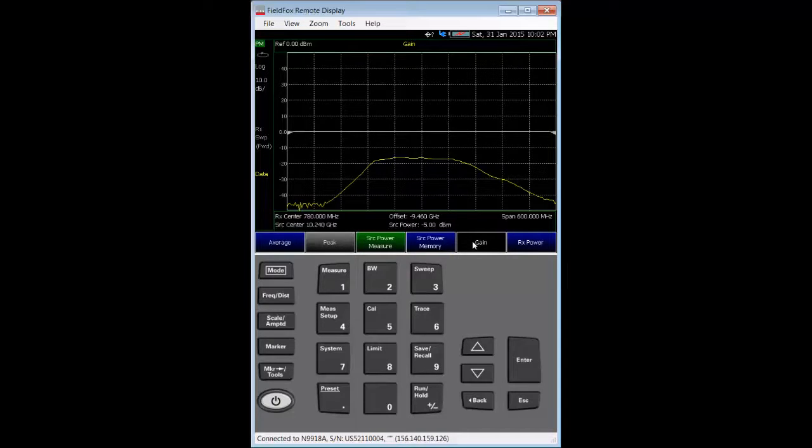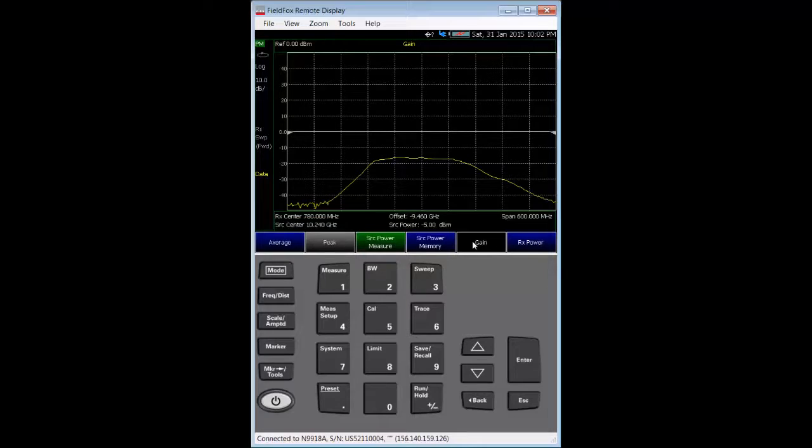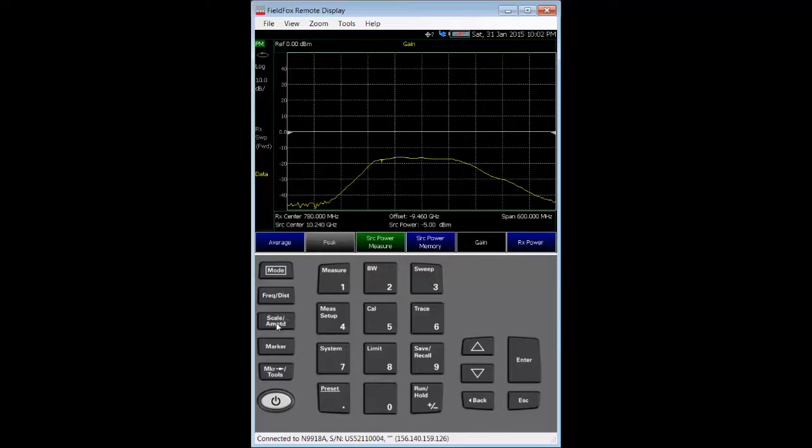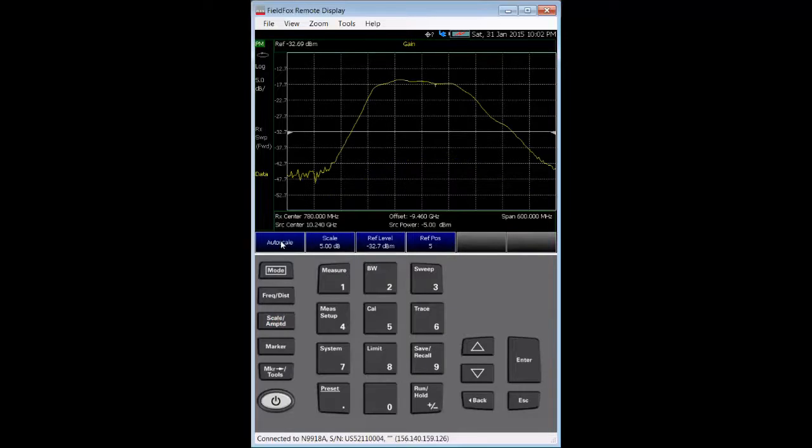With the DUT reconnected, I pressed the gain soft key. Finally, I autoscale the measurement using the scale amplitude hard key and the autoscale soft key.